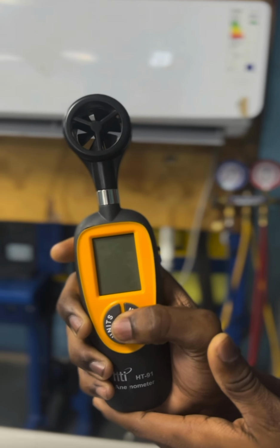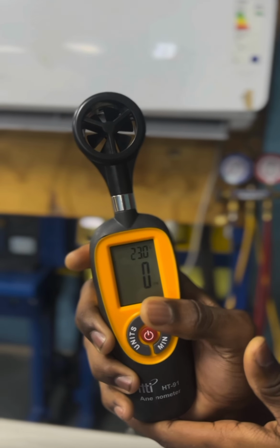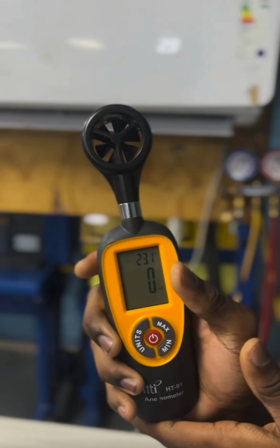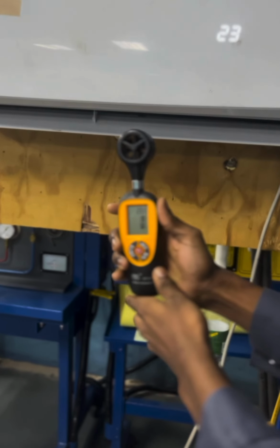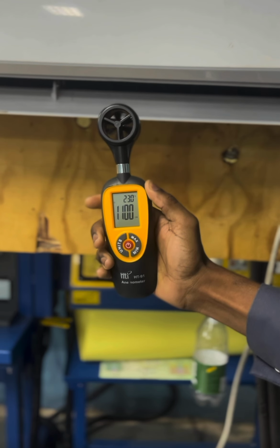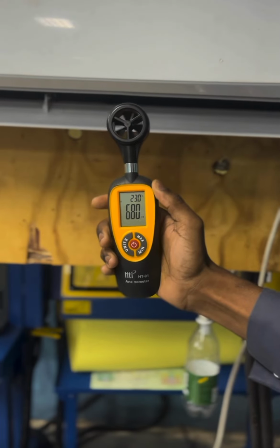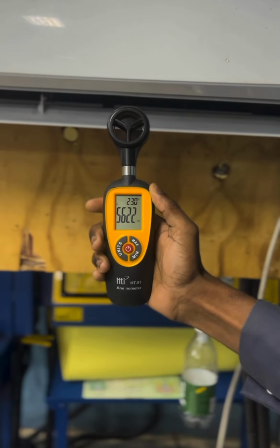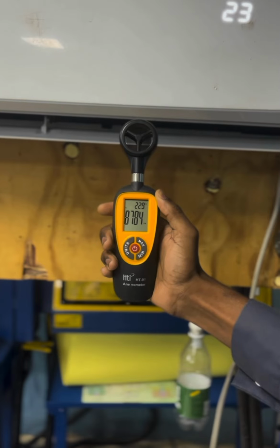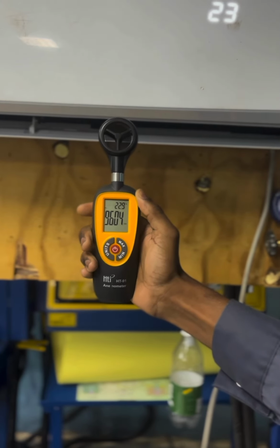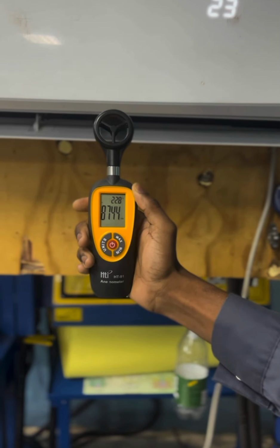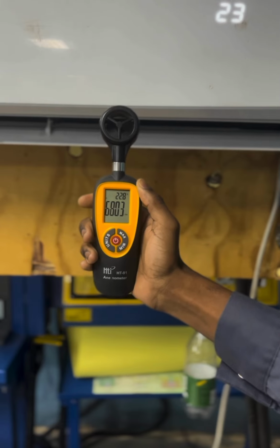Firstly, turn on the anemometer. Secondly, place the sensor directly in the airflow path. Thirdly, hold it steady for a stable reading. Fourth, record the air velocity in feet per minute or meters per second. Multiply velocity by duct area to calculate airflow. Lastly, we adjust the dampers to increase or decrease airflow as needed.